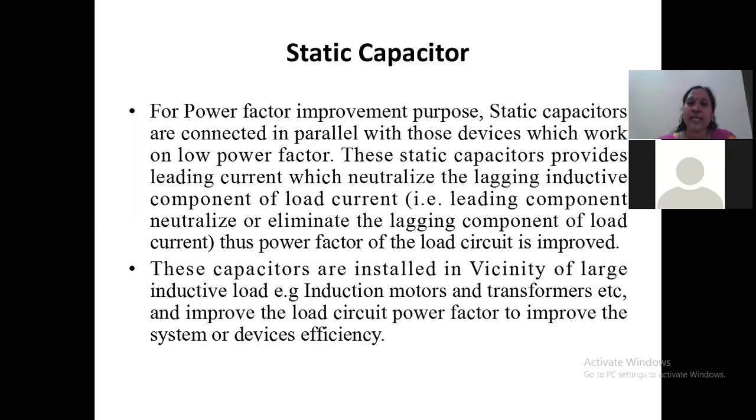These static capacitors provide the leading current which neutralizes the lagging inductive component of the load current. Since all the usual loads are inductive, we have to use capacitors for providing the reactive power. That is what this static capacitor is going to do. Thereby it is going to compensate the lagging inductive component, and thereby improving the power factor of the load.